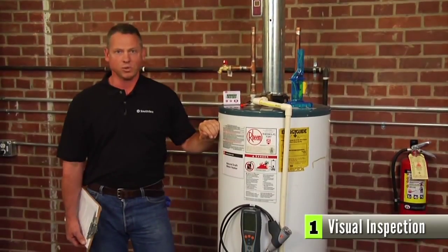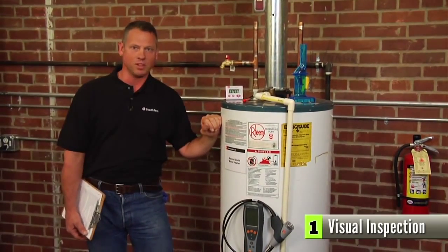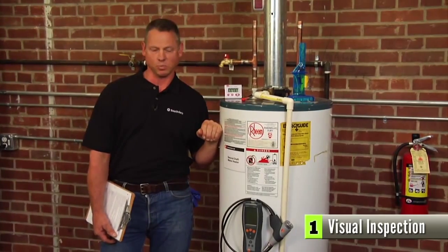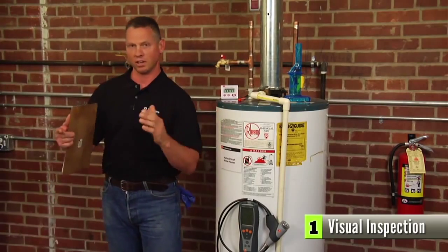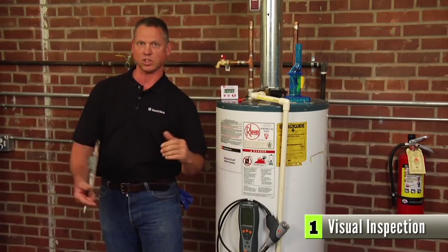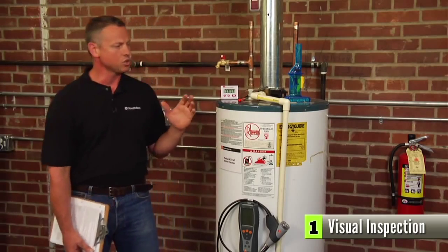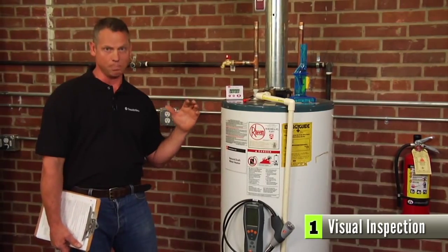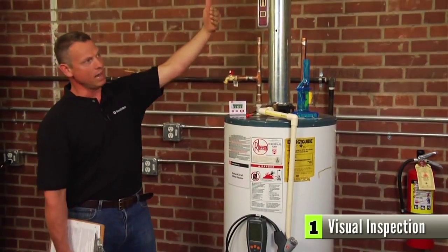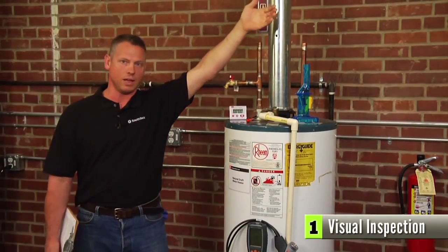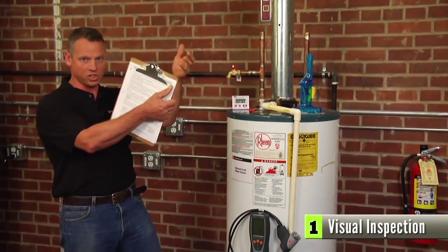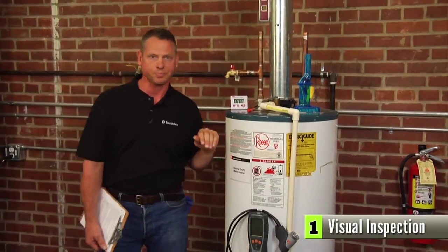Your visual inspection should also include the room where the combustion appliance is located, the combustion appliance zone, or CAZ. Identify if the CAZ is connected to the living space. This particular CAZ is connected to the living space. There's no door between this appliance and the rest of the house, so the whole house is essentially the combustion appliance zone. You also want to check for sneaky bypasses in the CAZ, such as band areas, rim joists, or false ceilings. A band joist might have gaps in it that could lead into the floor system and get into the rest of the house, and a false ceiling might allow flue gases to leak up into the ceiling and then escape into the rest of the house.